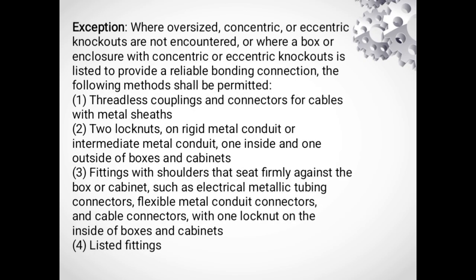Exception: where oversized concentric or eccentric knockouts are not encountered or where a box or enclosure with concentric or eccentric knockouts is listed to provide a reliable bonding connection, the following method shall be permitted. 1. Threadless couplings and connectors for cables with metal sheath. 2. Two lock nuts on rigid metal conduit or intermediate metal conduit, one inside and one outside of the boxes and cabinet. 3. Fitting with shoulders that seat firmly against the box or cabinet, such as electrical metallic tubing connectors, flexible metal conduit connectors and cable connectors with one lock nut on the inside of the boxes and cabinet.